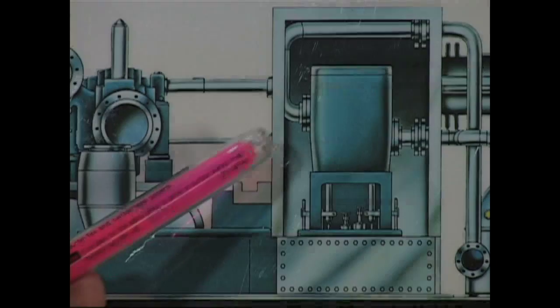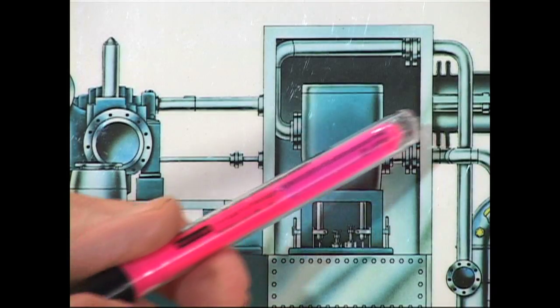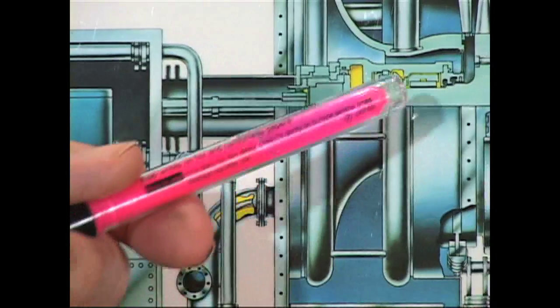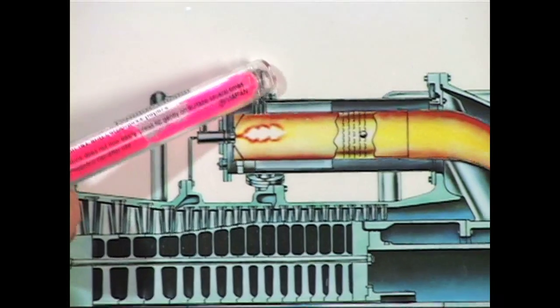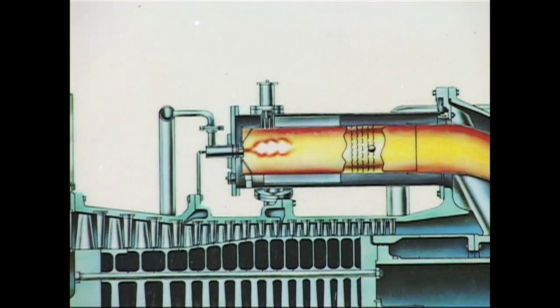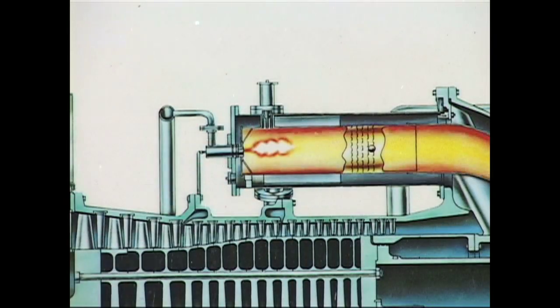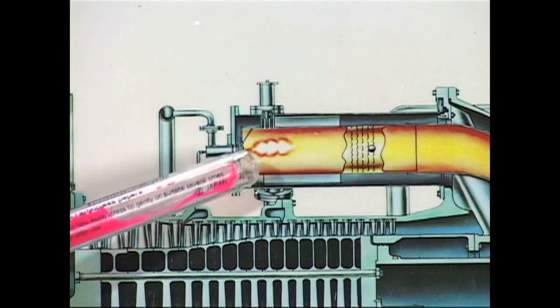When the machine has been brought up by the starting means to about 20 percent speed, then it's ready to fire. And it's fired by spark plugs on a couple of combustion chambers. And in between each combustion chamber, at least 10 chambers, is a crossfire tube.